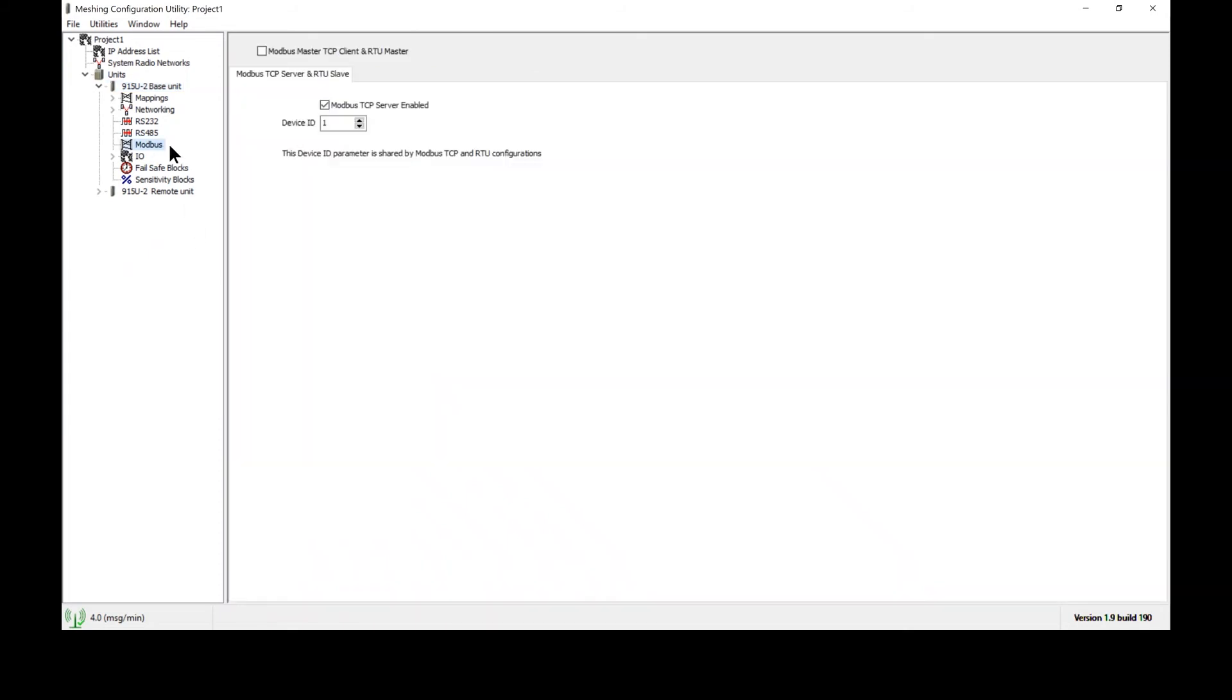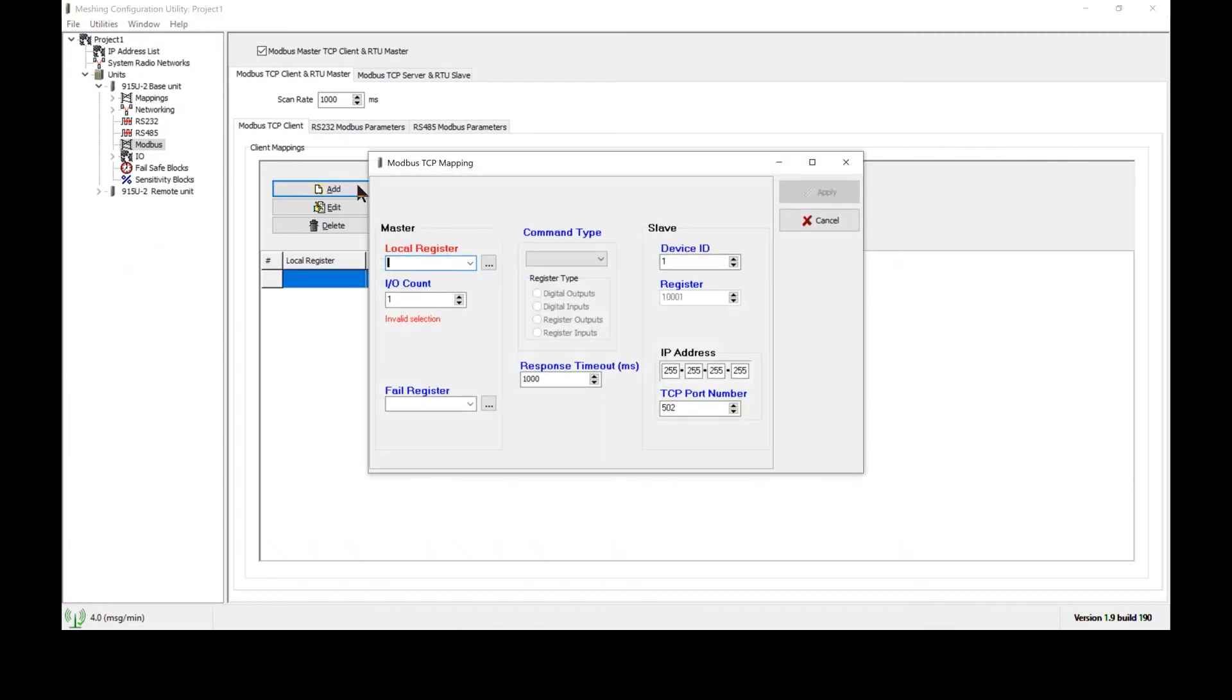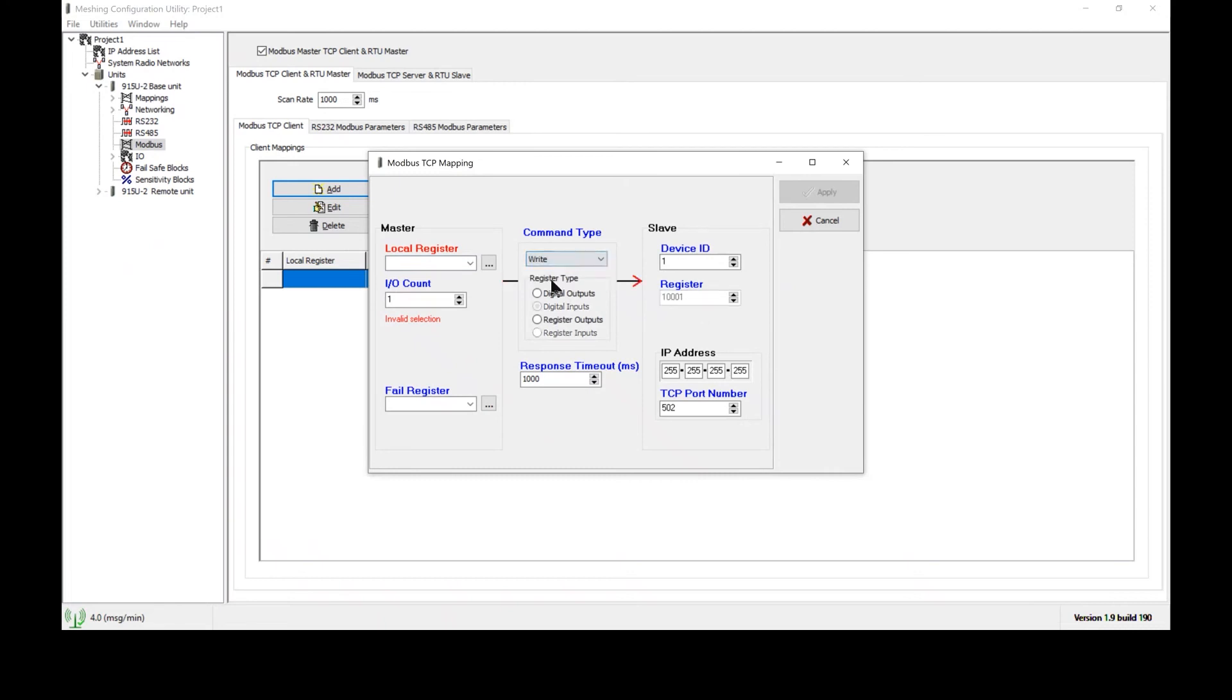Going back to our Modbus setup, if we wanted to set up a Modbus TCP master we need to enable this box here and now we see some additional parameters. This is the scan rate so this will send a Modbus master message once per second. We need to make Modbus TCP client mappings. To do so click on add and the next step is to select your command type.